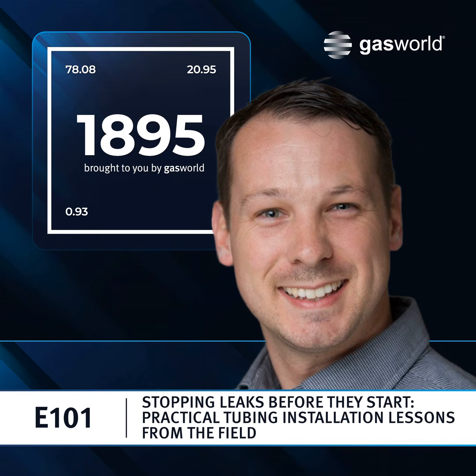We talked a little bit about gap inspection gauges. So once you install, you can always use a gap inspection gauge to make sure that there is proper clearance and proper pull-up on the fitting. One of the things that we stress as much as possible is to do kind of an in-process inspection.